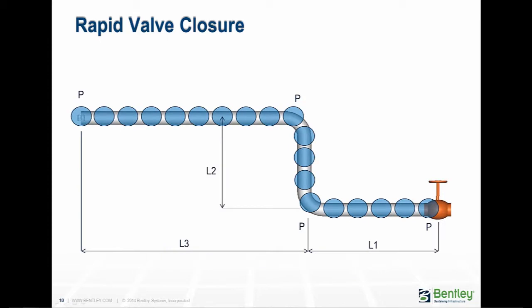If we ignore the change in pressure due to the change in height, the pipe system can be considered to have the same internal pressure throughout its length, illustrated by the blue circles. In AutoPIPE, the fluid transient module calculates the pressure rise at the valve using the Joukowsky's equation, and the speed of sound of the wave using Korteweg's equation. Knowing the geometry of the piping system, the program can automatically calculate the time histories for each part of the system as the wave travels through it.